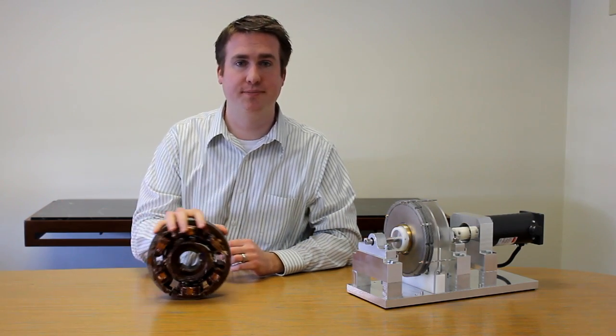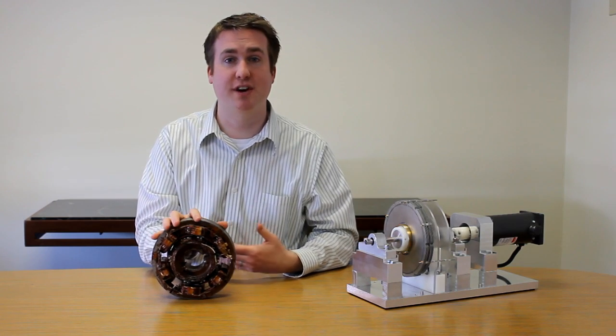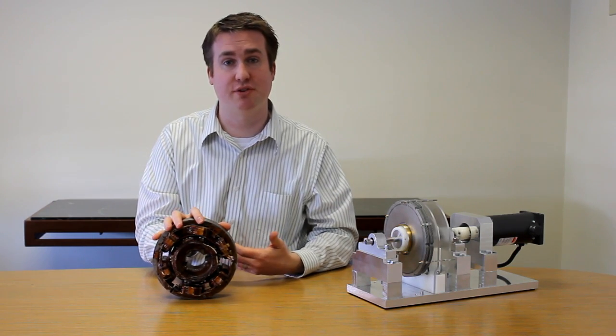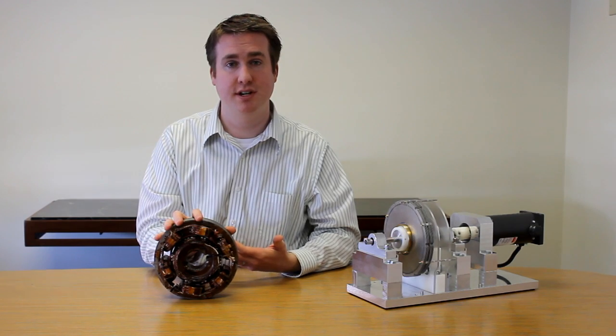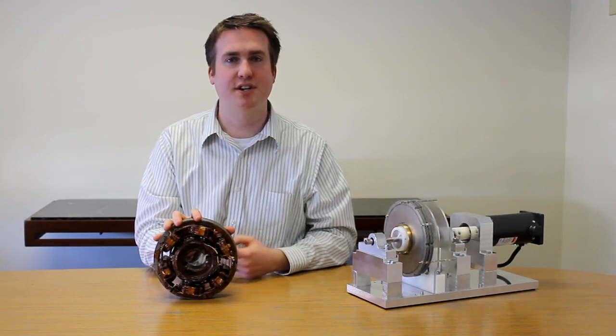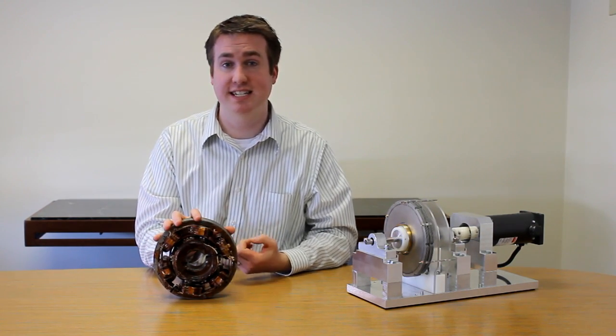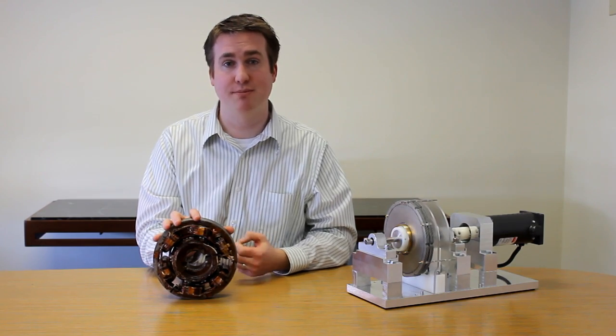These maintenance costs for slip ring assemblies have led to the use of non-contact solutions in many applications, namely the brushless exciter. Brushless exciters provide power to the rotor windings of the generator without brushes and their maintenance requirements. However, brushless exciters are bulkier than slip rings, less electrically efficient, and considerably more expensive.